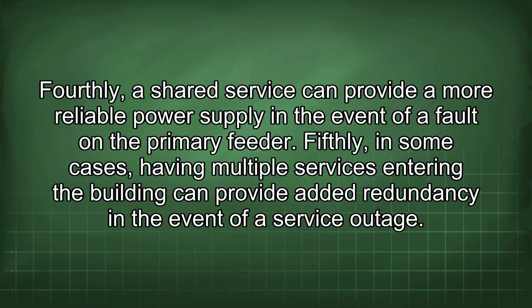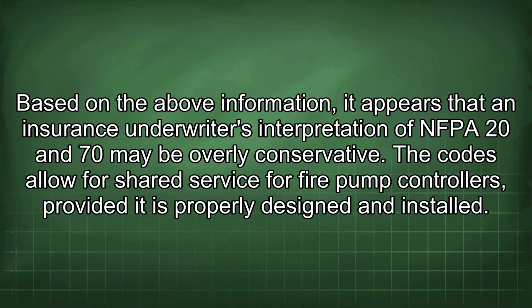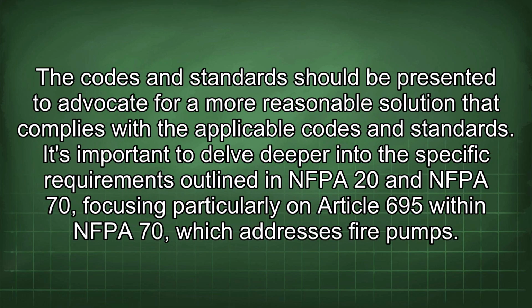Fourthly, a shared service can provide a more reliable power supply in the event of a fault on the primary feeder. Fifthly, in some cases, having multiple services entering the building can provide added redundancy in the event of a service outage. Based on the above information, it appears that an insurance underwriter's interpretation of NFPA 20 and 70 may be overly conservative. The codes allow for shared service for fire pump controllers, provided it is properly designed and installed. The codes and standards should be presented to advocate for a more reasonable solution that complies with the applicable codes and standards.